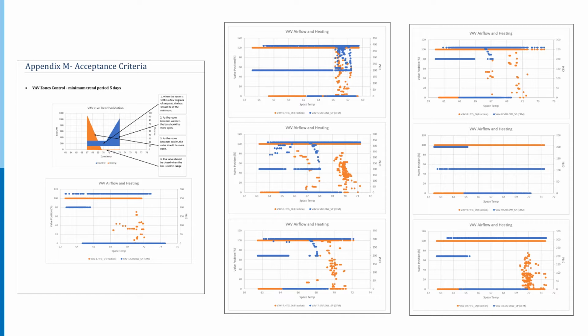So when I look at these, the first thing I look at is the width of the data. So from right to left, that tells you how tight your control is, right? If you were within 2 degrees or 3 degrees, then everything would be crunched together in a nice 2-degree band. So obviously in these zones, we have some very wide sways in temperature.